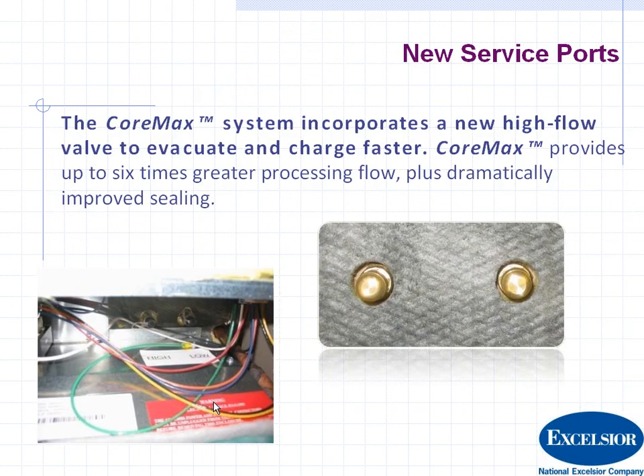Here is the question about the charging ports. These units have two charging ports, high and low side. Most of the others out there have just one charging port, and these are CoreMax charging ports, so you have a higher flow rate, so you can evacuate or charge faster. And that would really come in handy as far as less time spent in the customer's apartment or condo. You don't want to spend a lot of time in there. And also, it has a greater integrity as far as sealing. They'll have less leaks. But there are two suction and discharge ports here.